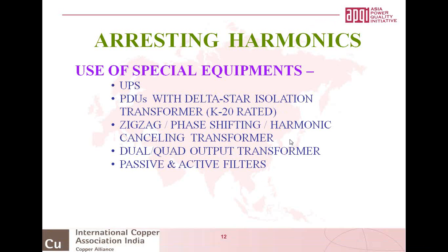UPS, when you use it, you can see in this slide that if the harmonics in the load towards the electronic loads and computers and servers could be anywhere between 70 to 100%, a UPS will reduce it effectively to somewhere between 3 to 30%, depending on the kind of UPS that one is using.